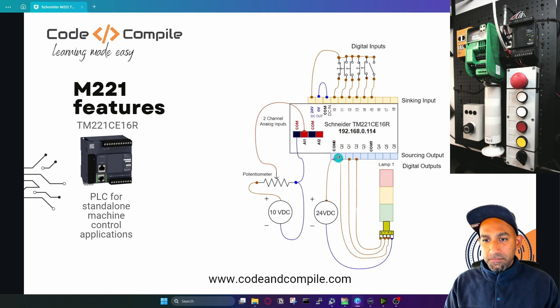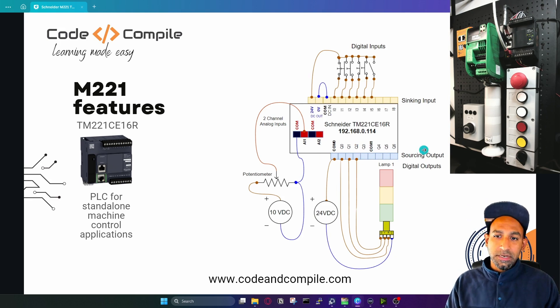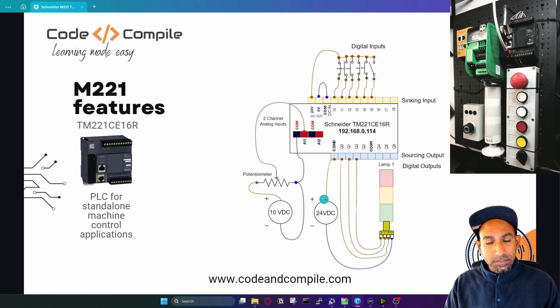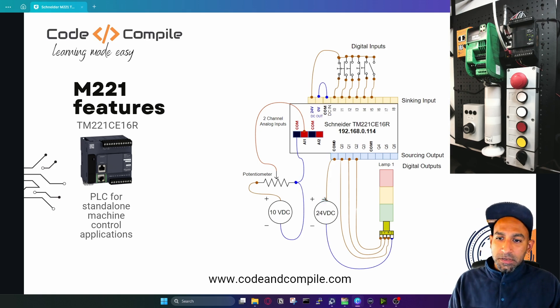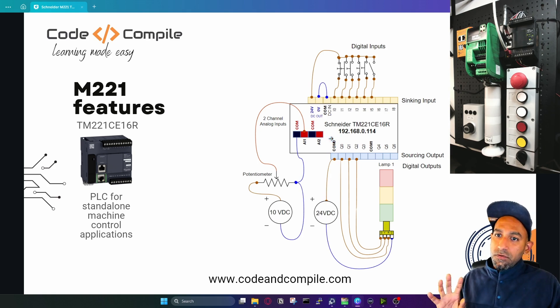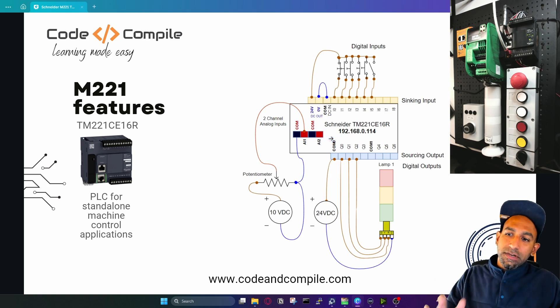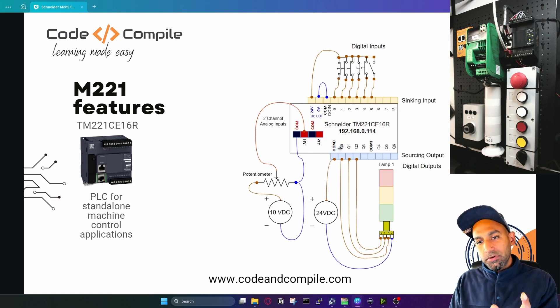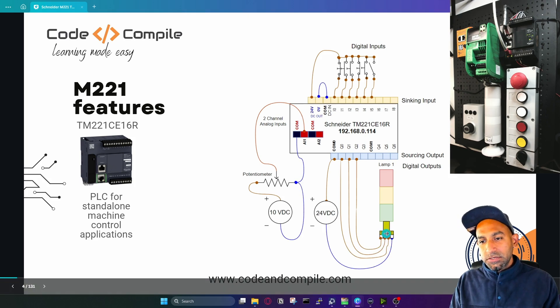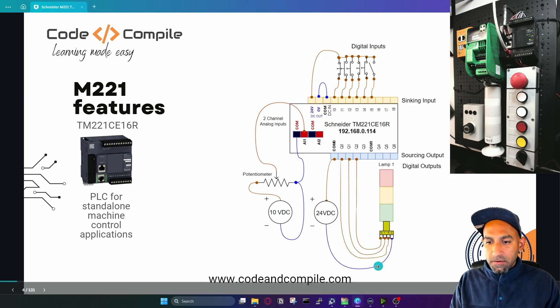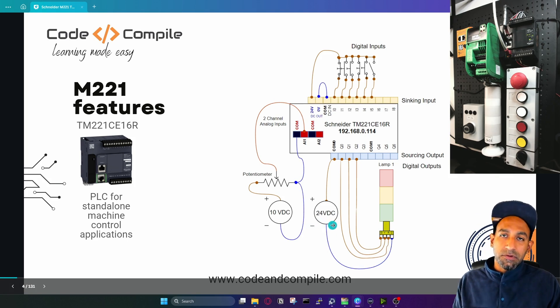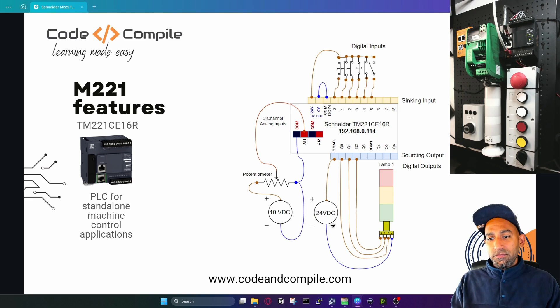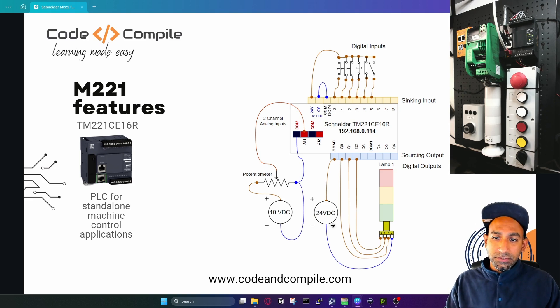On the output side we have common and Q0, Q1, Q2 — Q3 is not connected — and comm one for Q4, Q5, Q6, which are also not connected. To the common, we supply 24 volts. When the output is on, it supplies 24 volts outside, sourcing the 24 volt to the load — the load being a lamp. The 24 volt will connect to Q0 when Q0 is on in the program, and then Q0 will travel to the respective LED. The common of this lamp is connected to zero volts, so the lamp will be on. We maintain 24 volt potential difference to turn on the load.